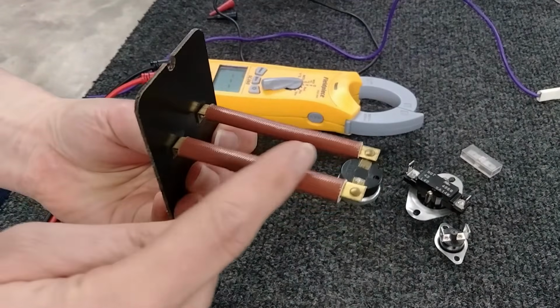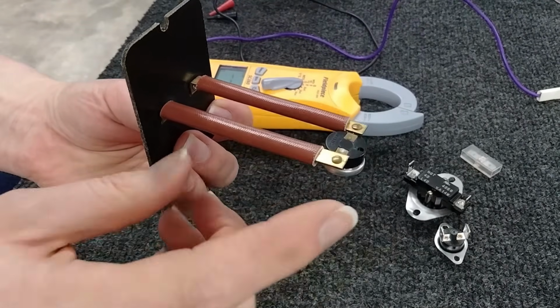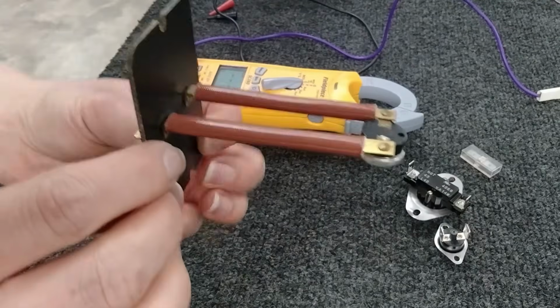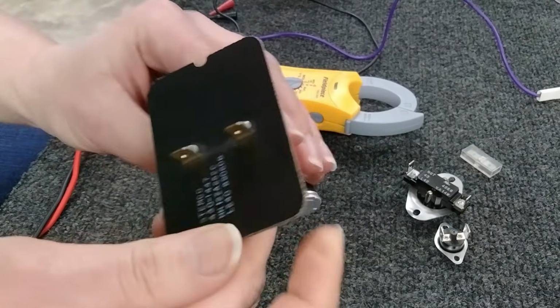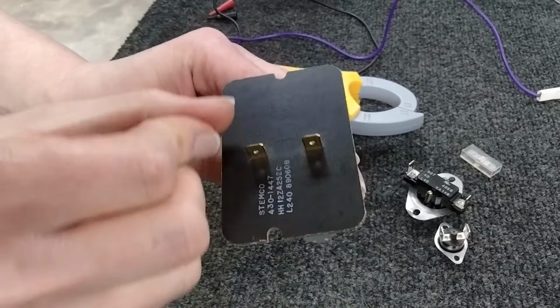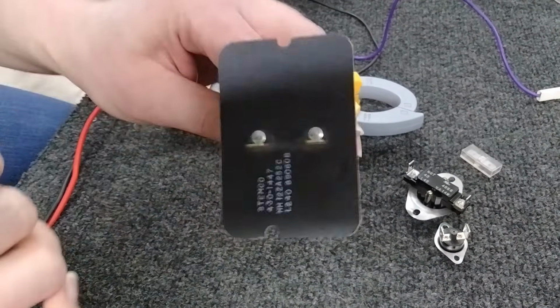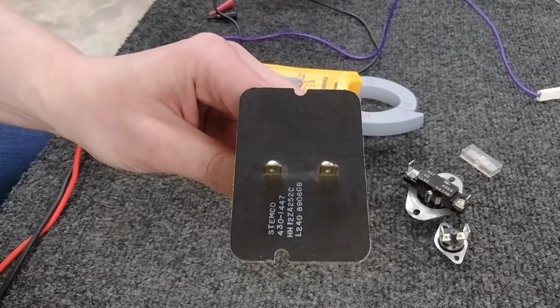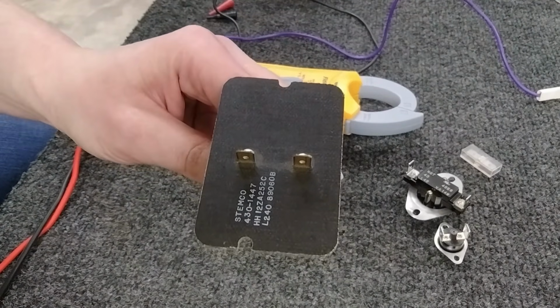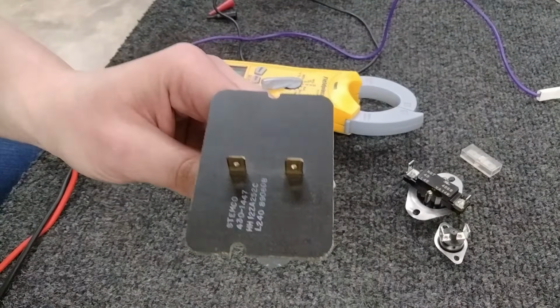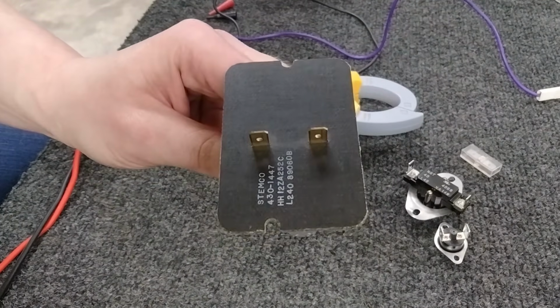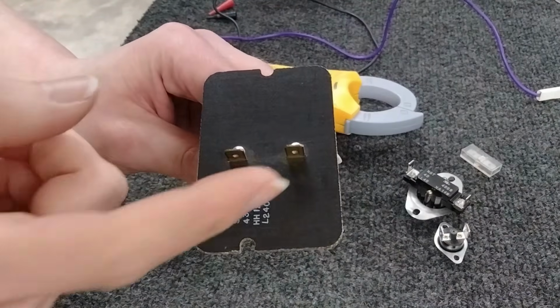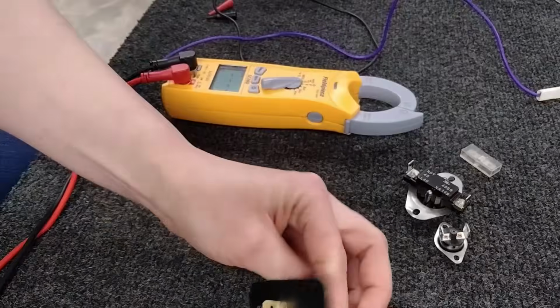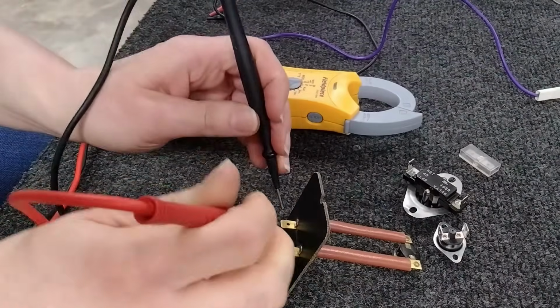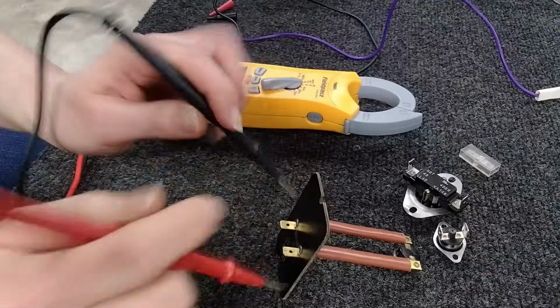Now, with a high limit switch, you're not going to see this back part of it right away, because this is actually the probe that goes back into your heat exchanger. What you're going to see from the front, some of yours might be flipped this way, is 2 prongs, and it's going to be mounted on your heat exchanger, usually back behind the gas valve. Somewhere on the metal wall, you'll see these 2 prongs. These, like the other limit switches, are going to be closed right away. So again, when you're testing your limit switches, this one should be closed. Right.